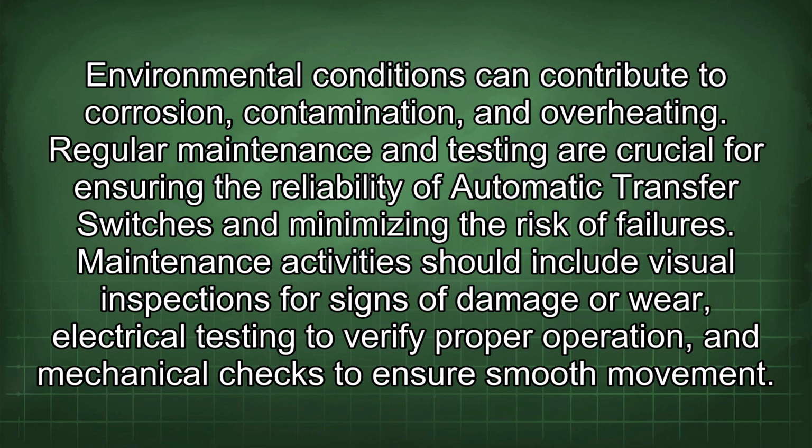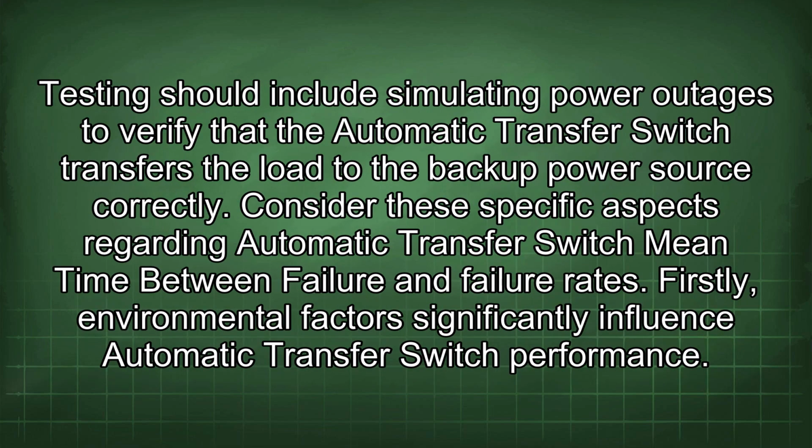Regular maintenance and testing are crucial for ensuring the reliability of automatic transfer switches and minimizing the risk of failures. Maintenance activities should include visual inspections for signs of damage or wear, electrical testing to verify proper operation, and mechanical checks to ensure smooth movement. Testing should include simulating power outages to verify that the automatic transfer switch transfers the load to the backup power source correctly. Consider these specific aspects regarding automatic transfer switch mean time between failure and failure rates.